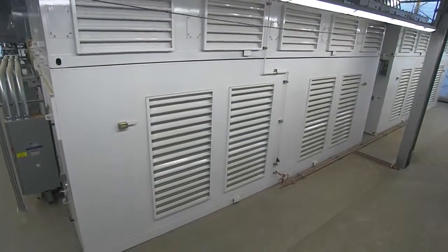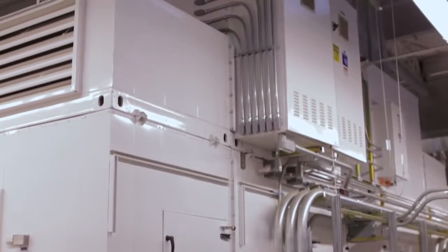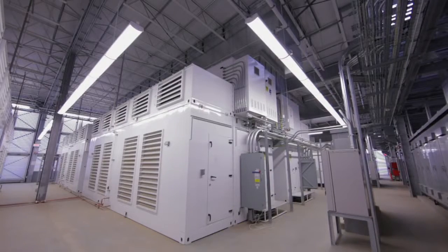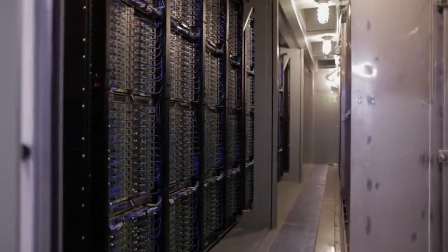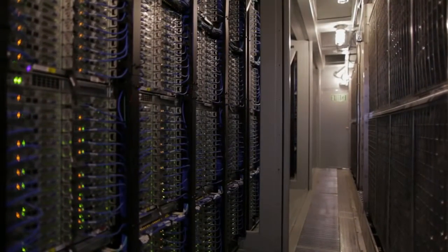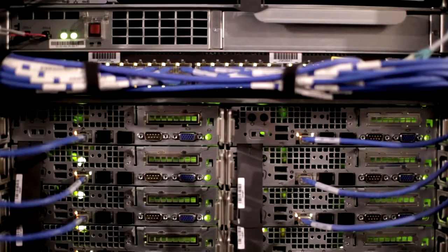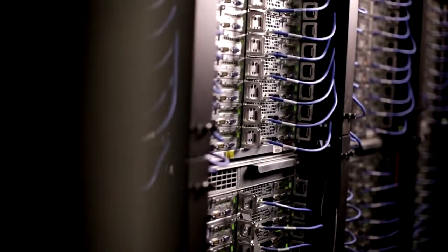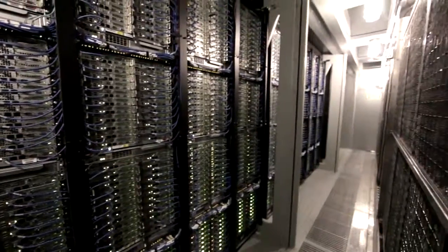Our Generation 4 facility utilizes air-cooled, IT pre-manufactured components, or IT packs. These state-of-the-art pre-assembled plug-and-play modular components can be manufactured in many locations through a dynamic supply chain of globally distributed vendors and use recyclable materials such as steel and aluminum, which are then shipped on-site and assembled. IT packs allow rapid commissioning of additional compute capacity as the business needs it, reducing the typical 2-year construction timeframe in half and reducing capital costs by 30 to 50% over the lifetime of the facility.